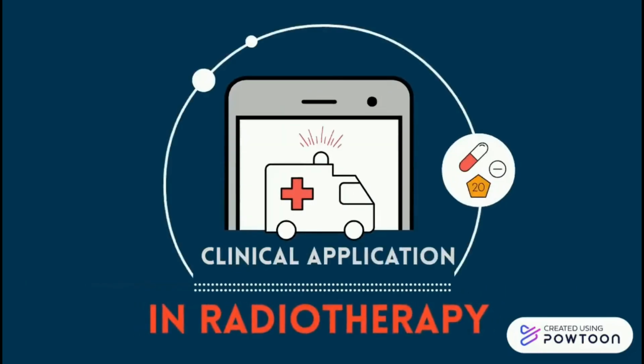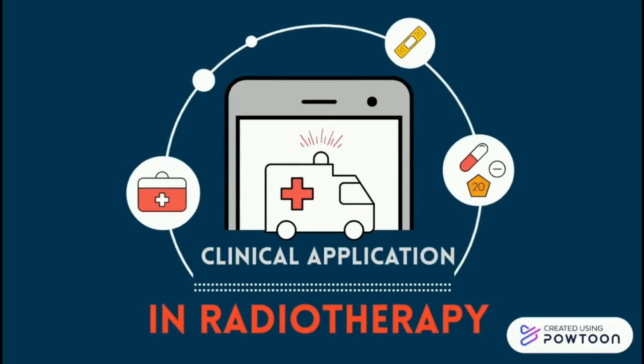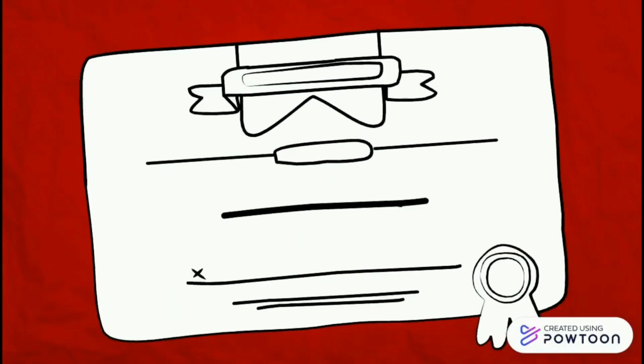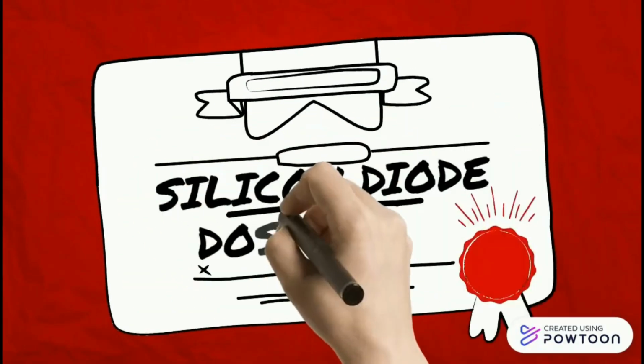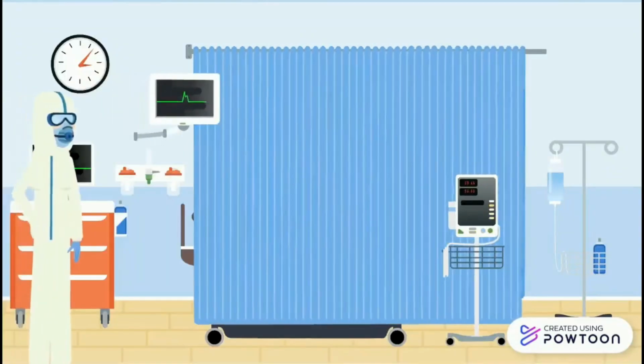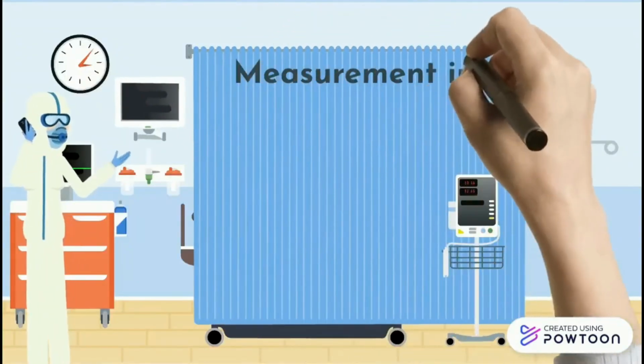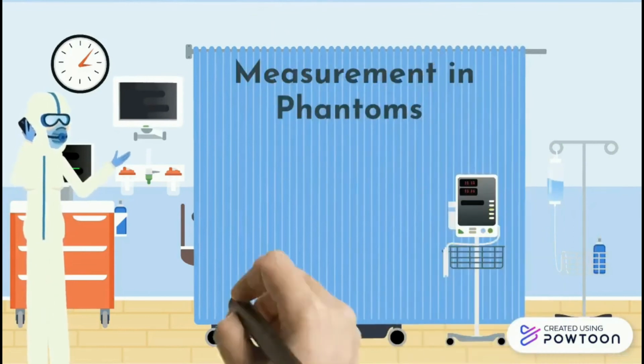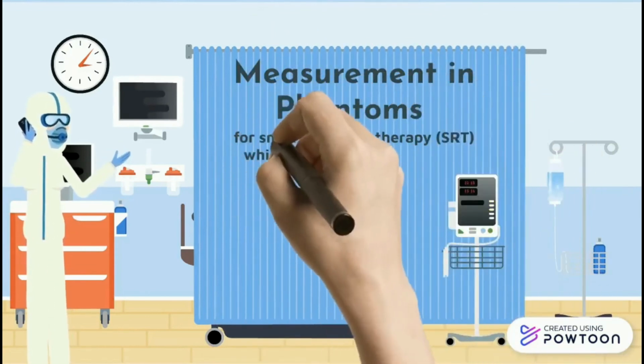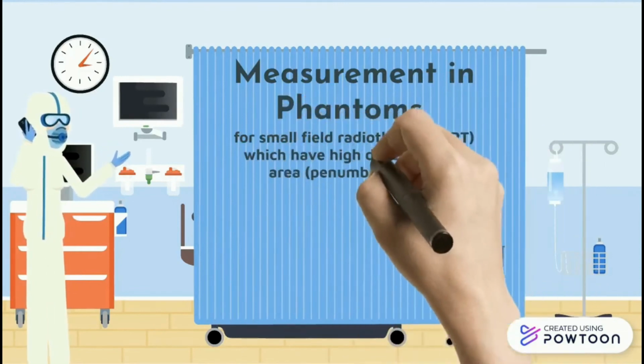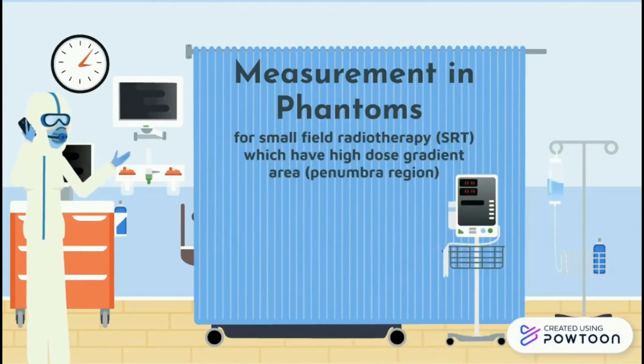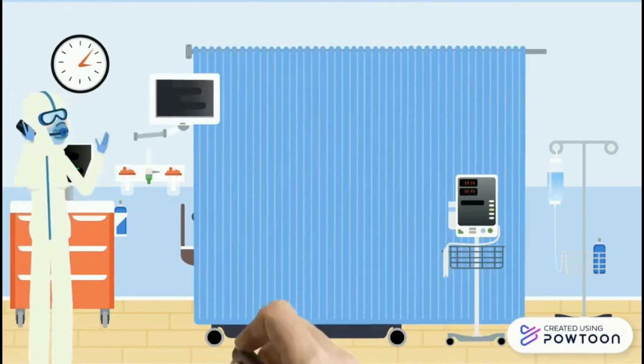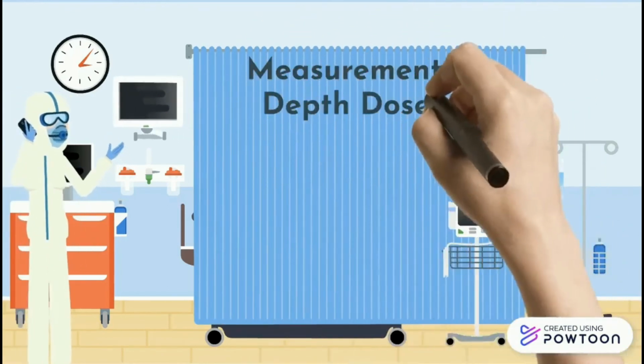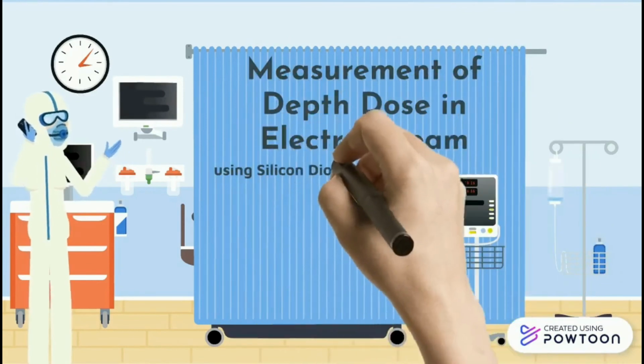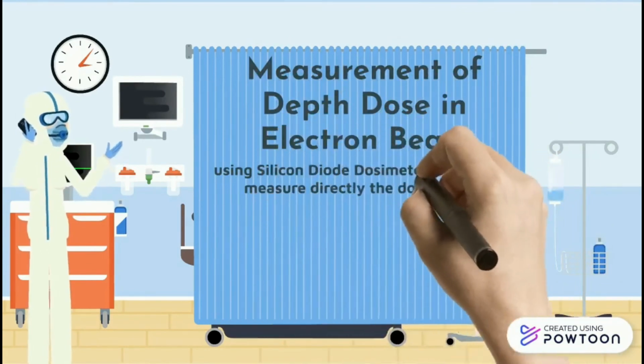Okay, now we are going to look at the clinical application of semiconductor dosimeter in radiotherapy. The first one is the measurement in phantoms, in which silicon diode dosimeter is used for small field radiotherapy or SRT, which have high dose gradient area or so-called the penumbra region. In electron beam, we can also measure the depth dose using silicon diode dosimeter, which produces directly the dose distribution measurement.